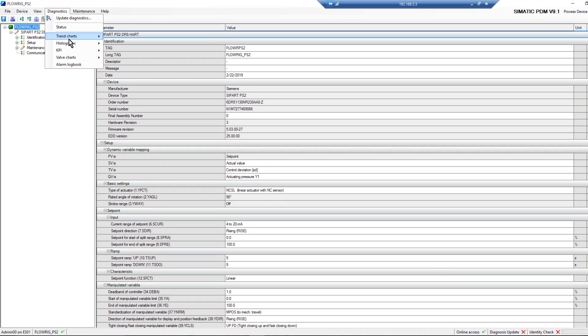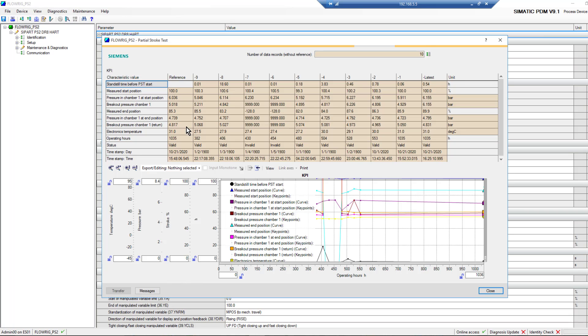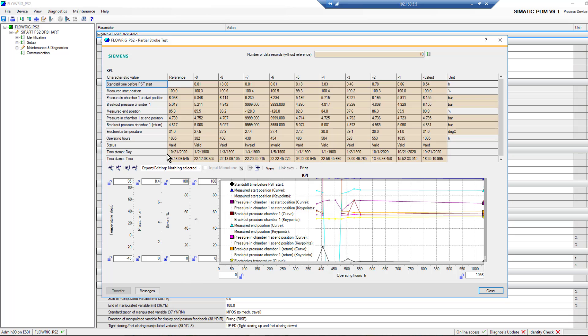Under Diagnostics and KPI, you'll see here partial stroke test. This is the beauty of KPIs - they simplify our results for us. I understand that looking at a valve signature is quite powerful and we can overlay those and see really advanced diagnostics. KPIs really focus on simplifying that data. You can see here, here's my reference which has got today's date on, and then you've got my last two tests which I've also done today, and these are my results. I'm basically monitoring these.